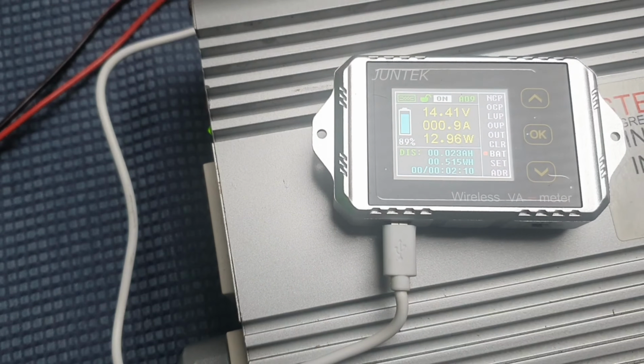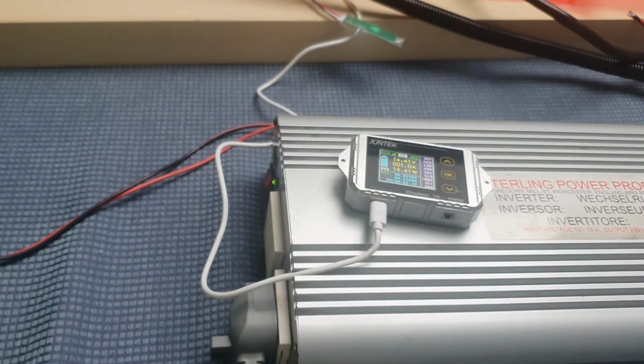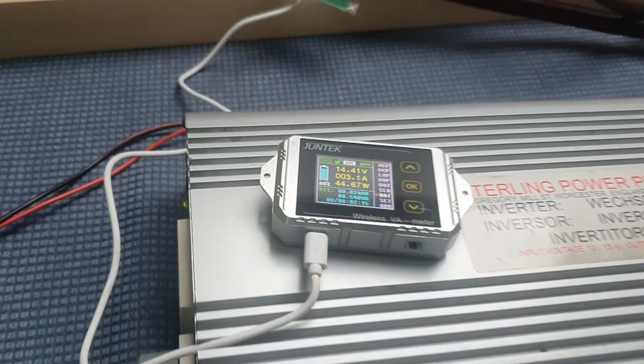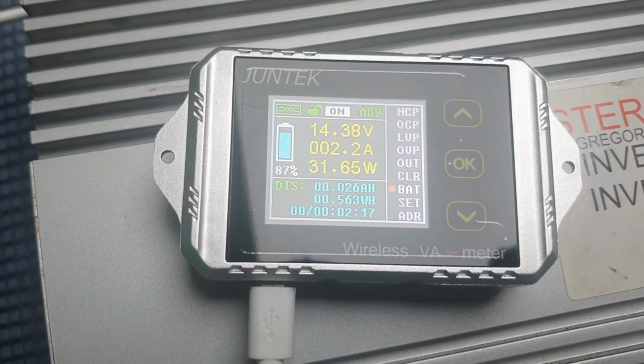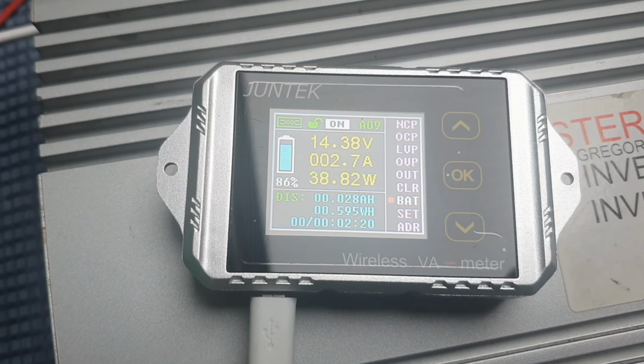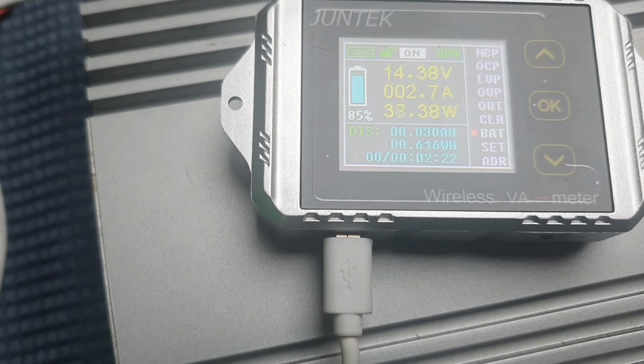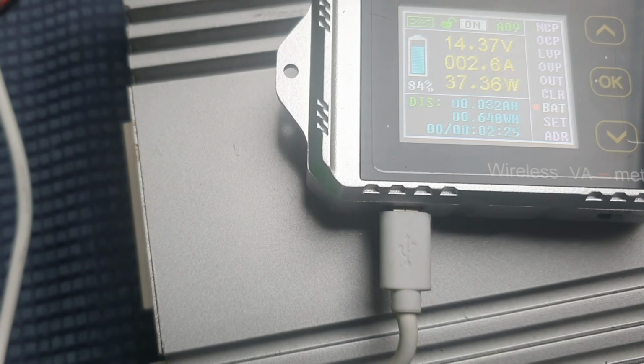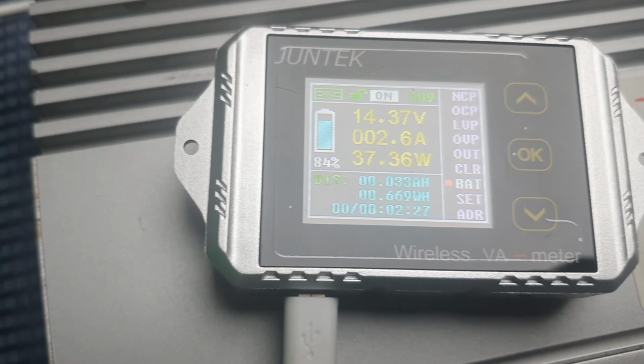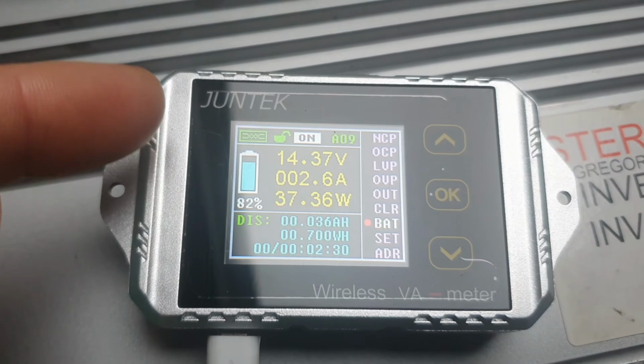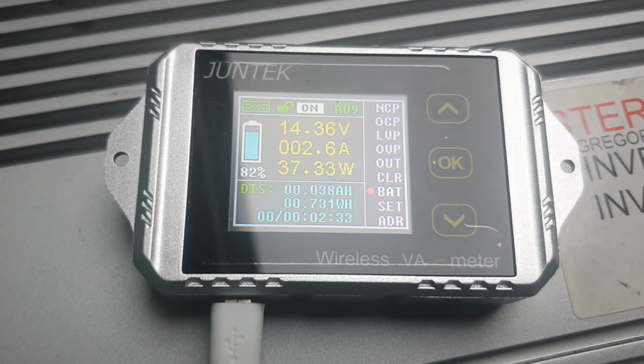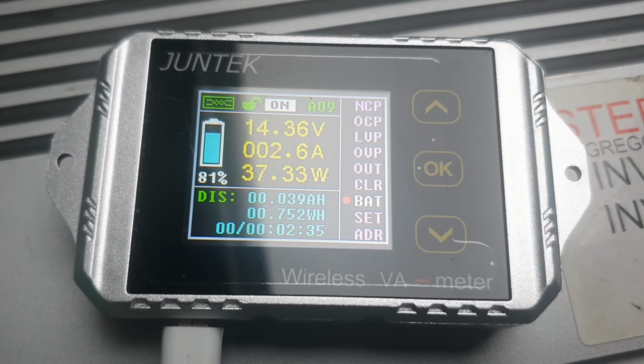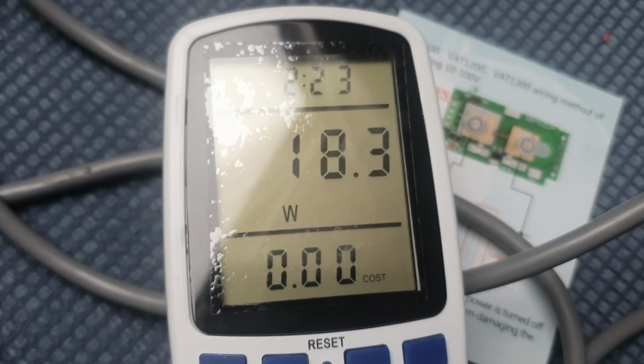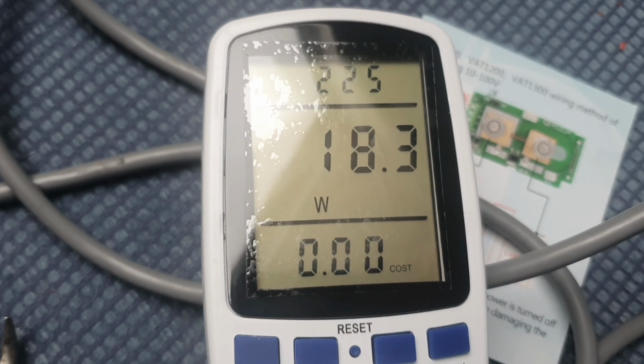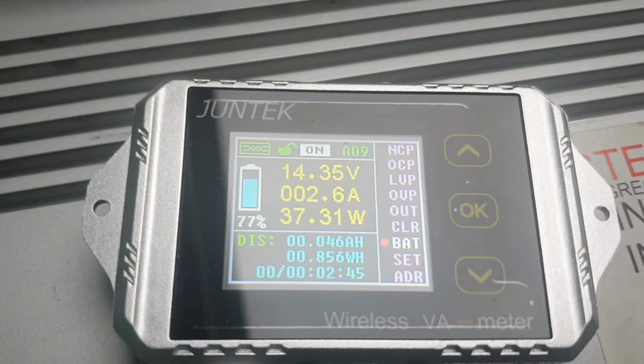Everything is ticking up, so at 12:30 we will start the test. First of all, as you can hear, on fan only, that's drawing about 2.7 amps. Let's just watch - ignore this battery level here, because I don't think that's accurate, it needs to run a couple of times. So it's drawing 40 watts there at 2 amps, and we're drawing 18 watts on the 240 side.